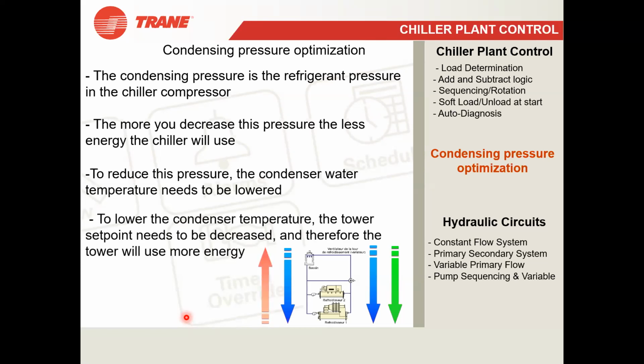You have to decrease the set point of the cooling tower, right? Because the cooling tower is sitting on top of everything. So you have decreased the cooling tower set point. That means the water temperature you are getting at the condenser gets lowered, and then the condenser water temperature will be reduced. By doing this you will achieve this, so your energy use will be very, very less.